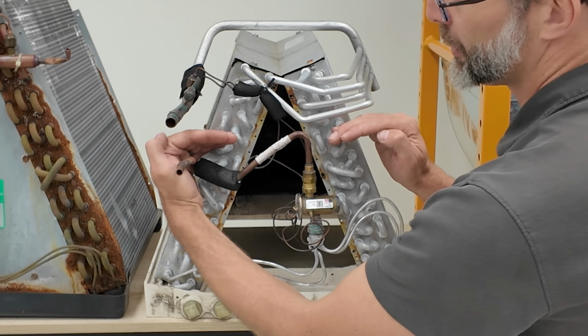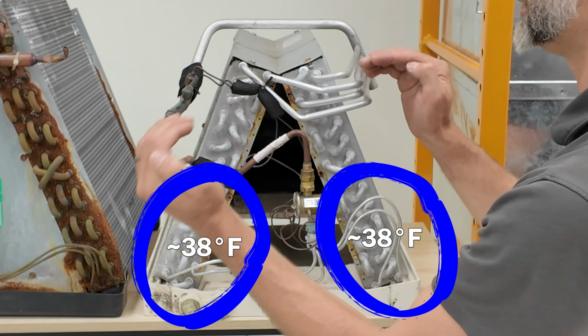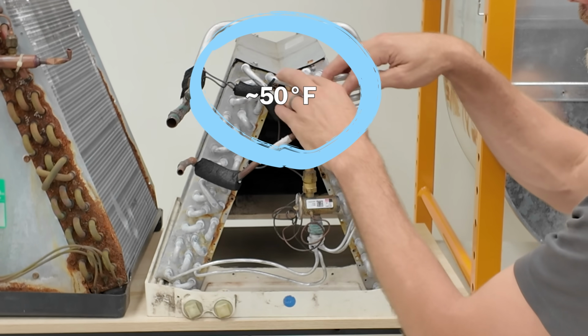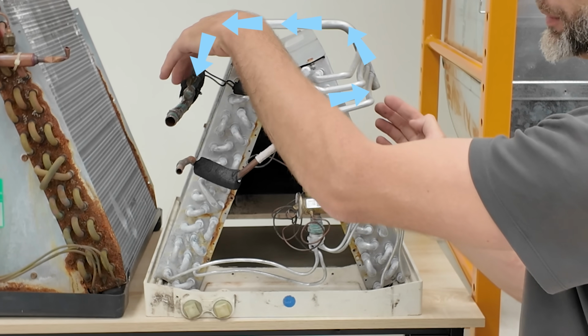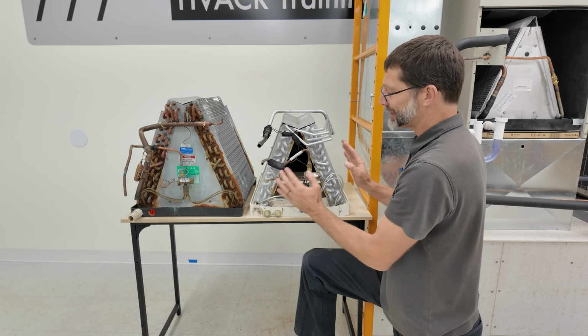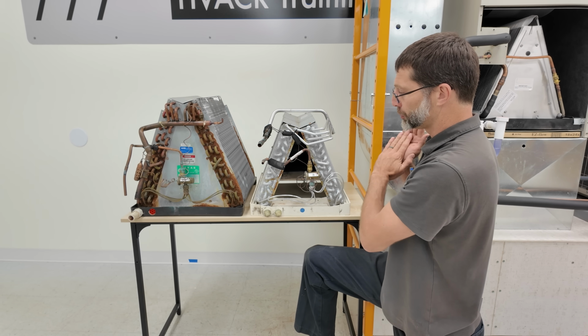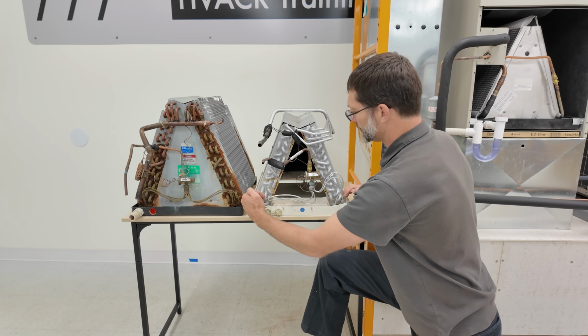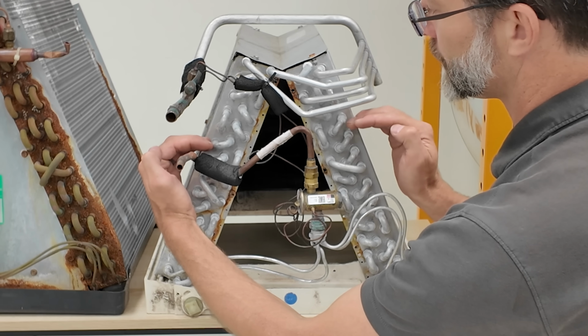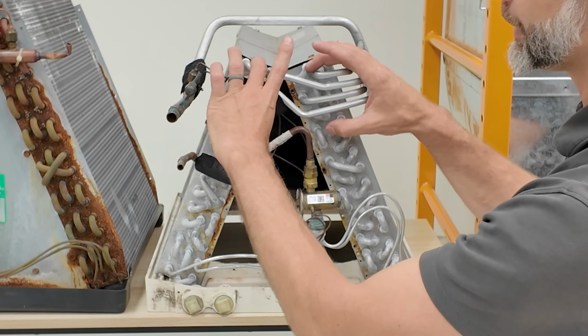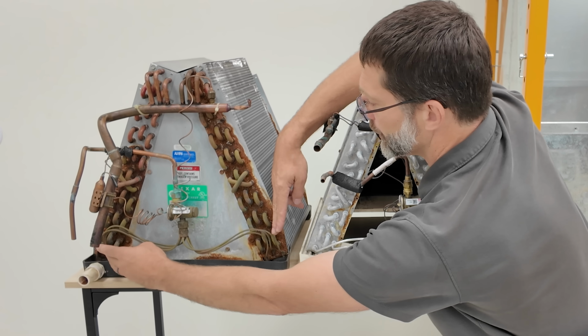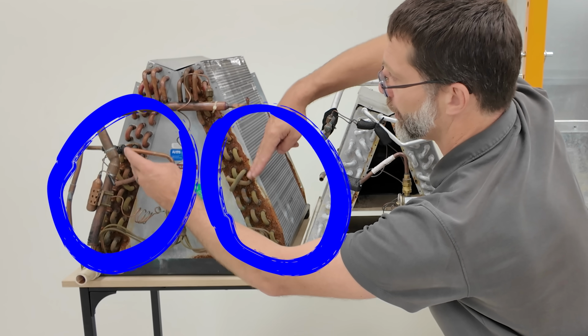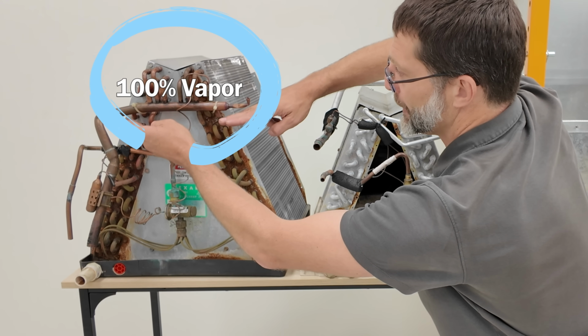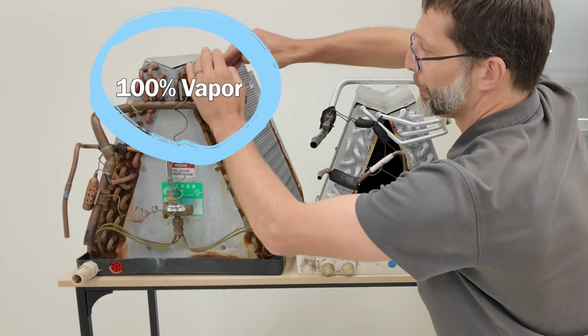Say it increases from, say, 38 degrees up to, say, 50 degrees, and then the vapor gathers back into the header tube and travels back to the compressor. So that's how this differs from the microchannel coil, because the phase change is occurring on both sides up to this point, and then it's vapor here and here. Same thing here. So the phase change is occurring from here all the way up to here, and then it's vapor from here up.